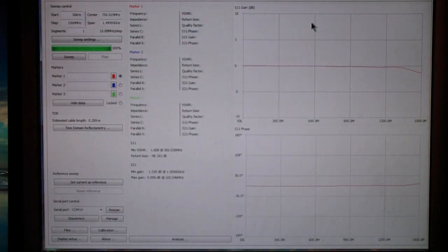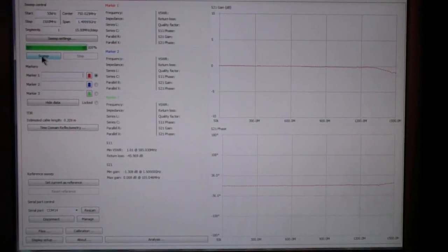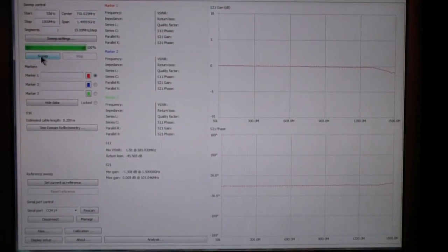So we have saved it, and this is the sweep of the through calibration. Now what we're going to do is one more sweep, and you notice that at the very end over on the right, let me turn the camera a little bit that way. There we go. You notice that there's a little droop at the high end. Now it looks like about a 1.5 to 2 dB droop, but still it is down at the high end.